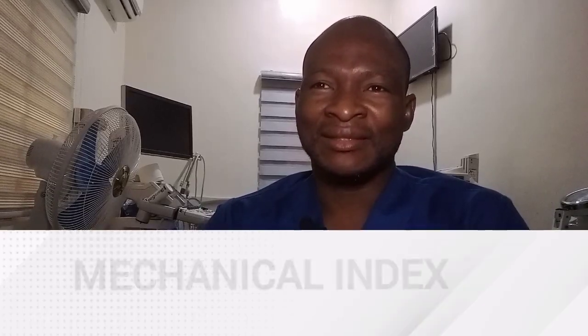Now, mechanical index is used to estimate acoustic outputs that have the potential for mechanical bioeffect called bubble formation or cavitation. A mechanical index that is greater than 1 does not indicate bioeffect. It rather describes that the potential for cavitation bioeffect has increased. The potential has increased, not that the cavitation is happening. The operator should ensure that the ALARA principle is being applied when you see this value. Look for ways to reduce potential exposure that will not compromise the diagnosis.